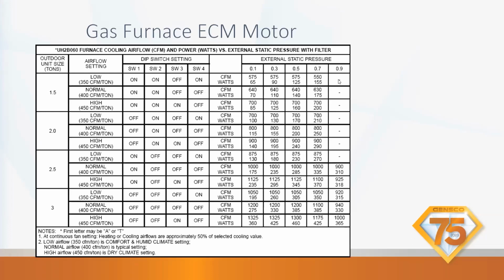Okay. On the left-hand side, that's the tonnage of your equipment. The next one is low, normal, or high. Is it for AC? You're going to set it at 350 for an air conditioner only. For a heat pump, you have to set it at 400. Okay, so all heat pumps need to be set at 400 for charging.